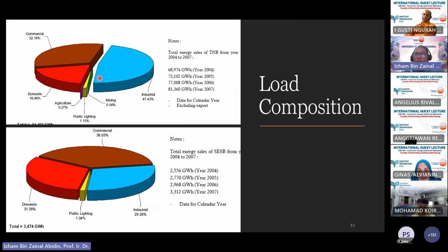For example, when we talk about domestic load, you're talking about more resistive and inductive load. The inductive load won't be as huge since it's mostly resistive, so you wouldn't have a lot of power factor problems, because typically in any domestic house you only have small pumps, maybe for your air conditioning or water pump, and most of the load is heating or lighting load.